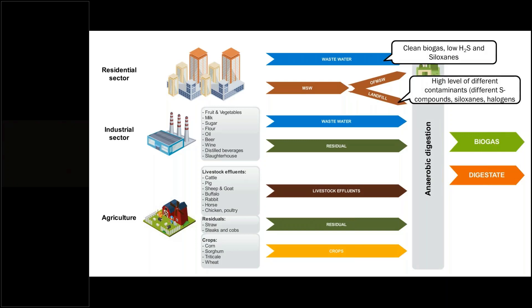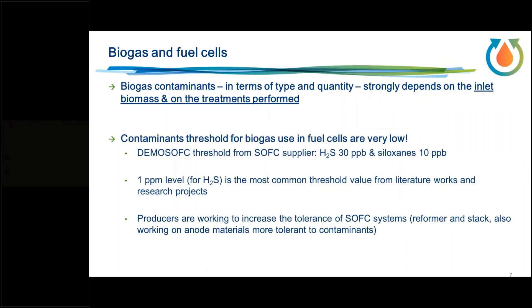Other biogas typologies include landfill gas, where contaminant levels are much higher — very high levels of different sulfur compounds such as mercaptans and thiols, siloxane, and halogens. Biogas from agriculture has significantly higher H2S compared to wastewater. These differences affect the type and scale of the required cleanup process. In our case with wastewater biogas, the levels are low enough that we concentrated on adsorption processes without scrubbing as a pre-step.